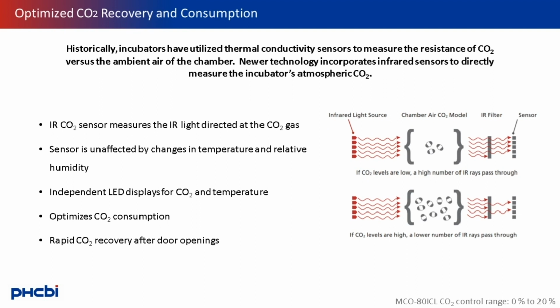Historically, the most common type of CO2 sensors were thermal conductivity sensors. These sensors measure the resistance of CO2 using the chamber's ambient air as a reference. Fluctuations in temperature and humidity can affect a TC sensor's ability to read the CO2 in the chamber. Infrared sensors measure the CO2 gas in the air directly. This type of sensor is unaffected by changes in incubator temperature or relative humidity. In order to accurately maintain desired CO2 levels, an infrared sensor measures the atmospheric CO2 in the gas directly.